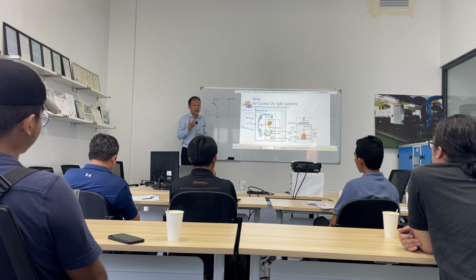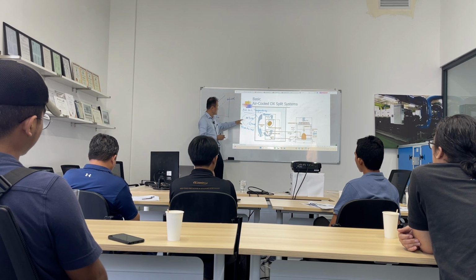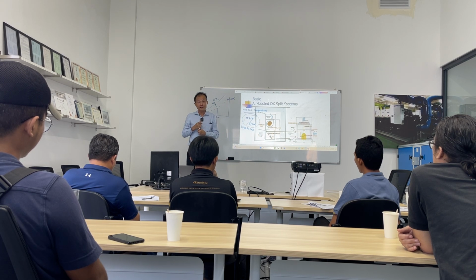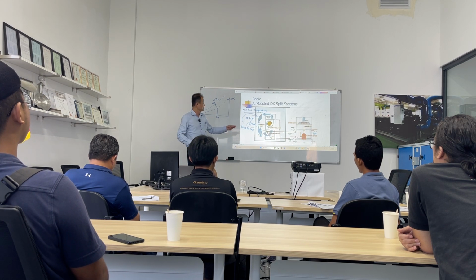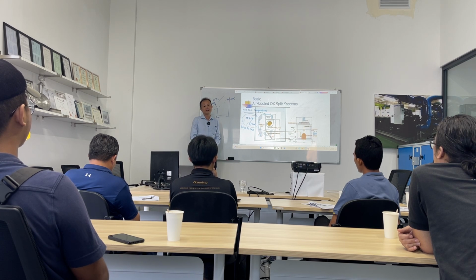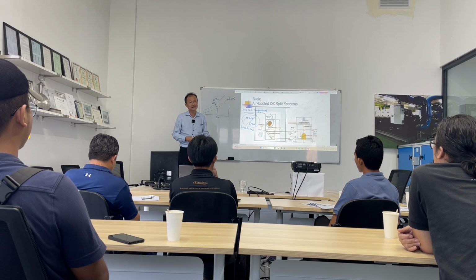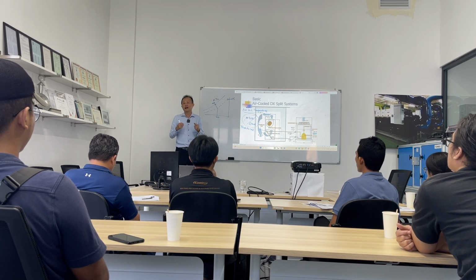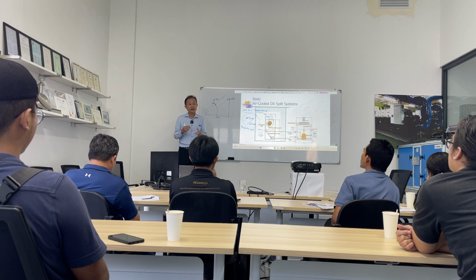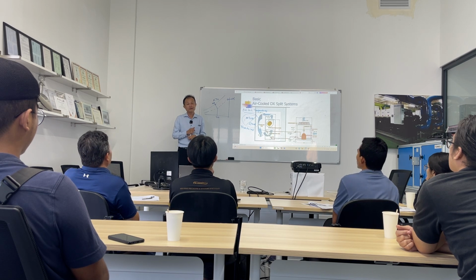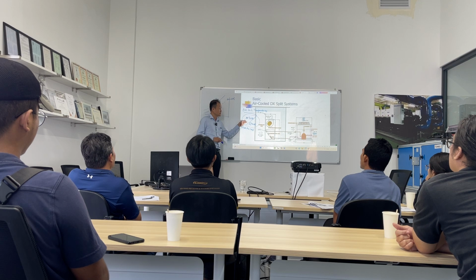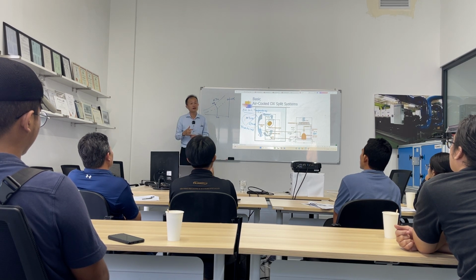No? But then you ask me, in the past, in many jobs, even though consultants did not account for these ratings, why was the coolness in a lot of buildings still no problem? Because in their heat load calculations, they already marked up so much. That markup already covered all this overrating. That means they got away because of oversizing. If, let's say, a consultant is aggressive and designs the heat load just tight, for example, and selects the standard rating of capacity from the catalog, surely it will not provide enough cooling.